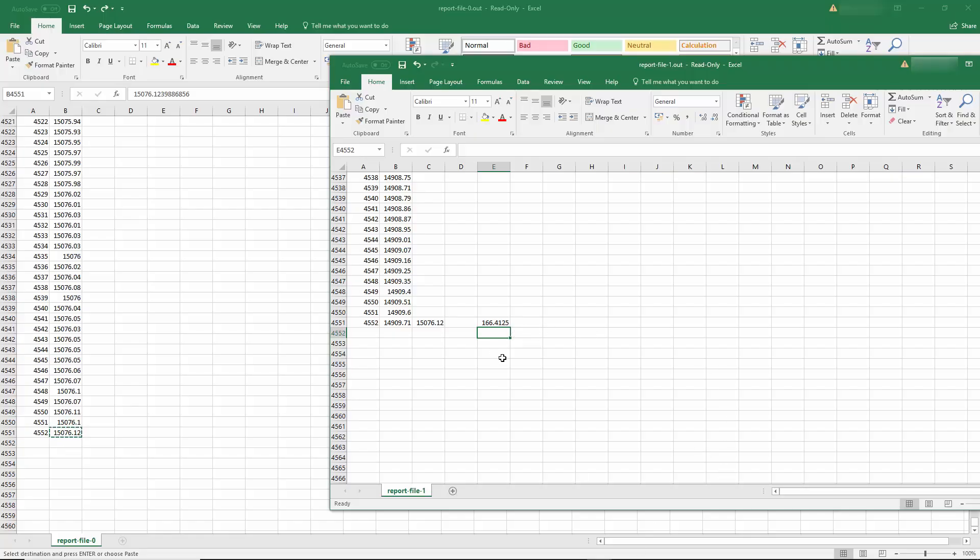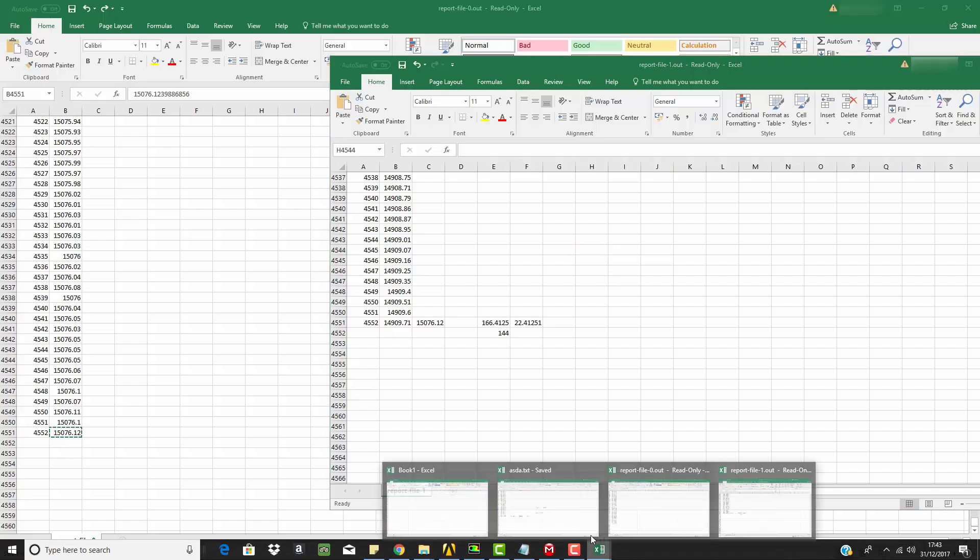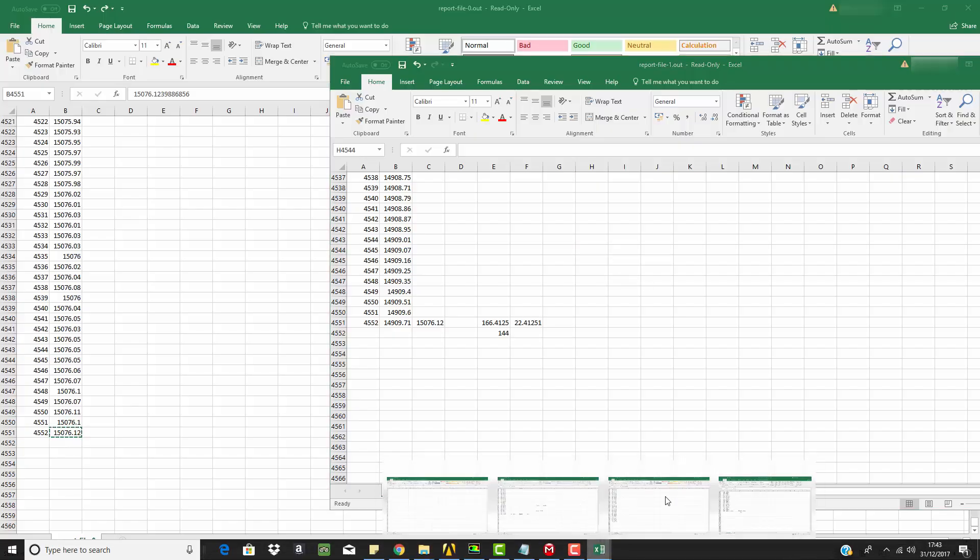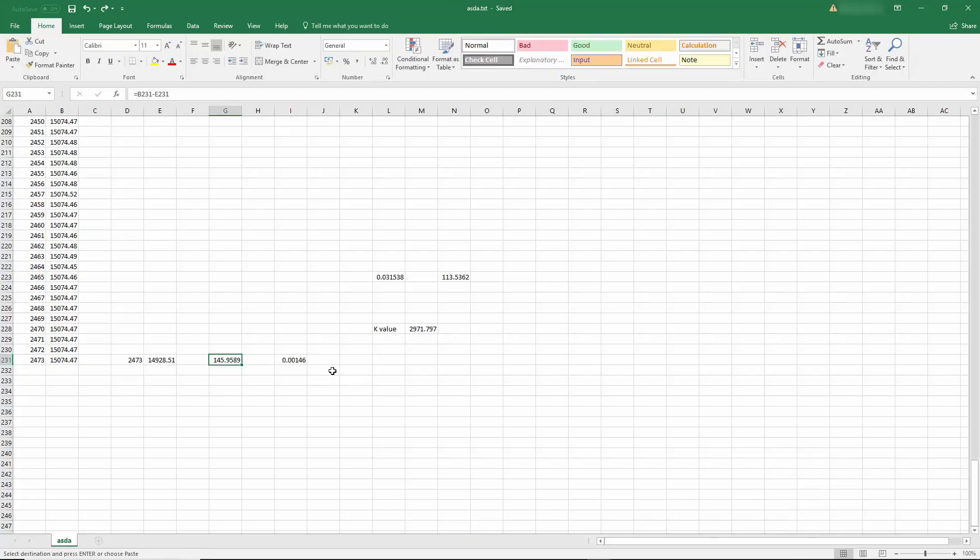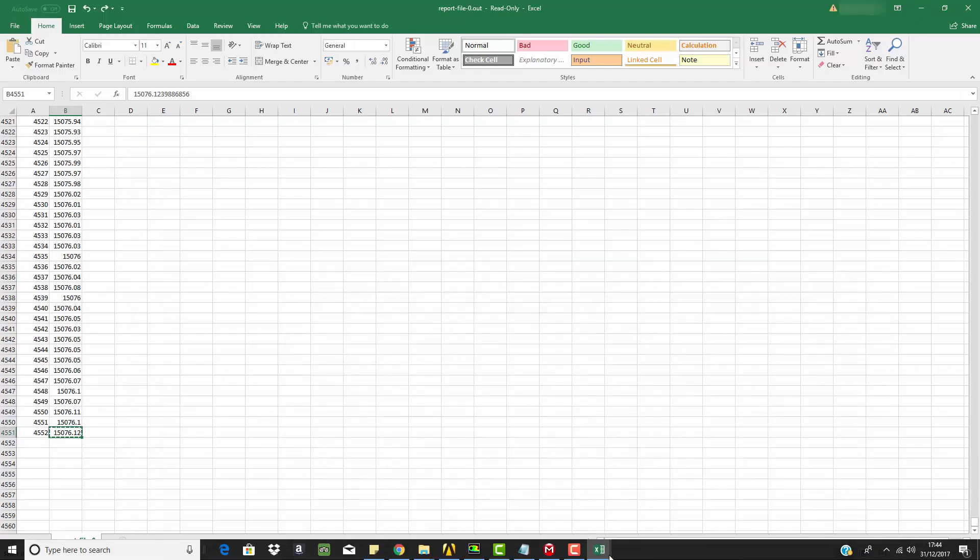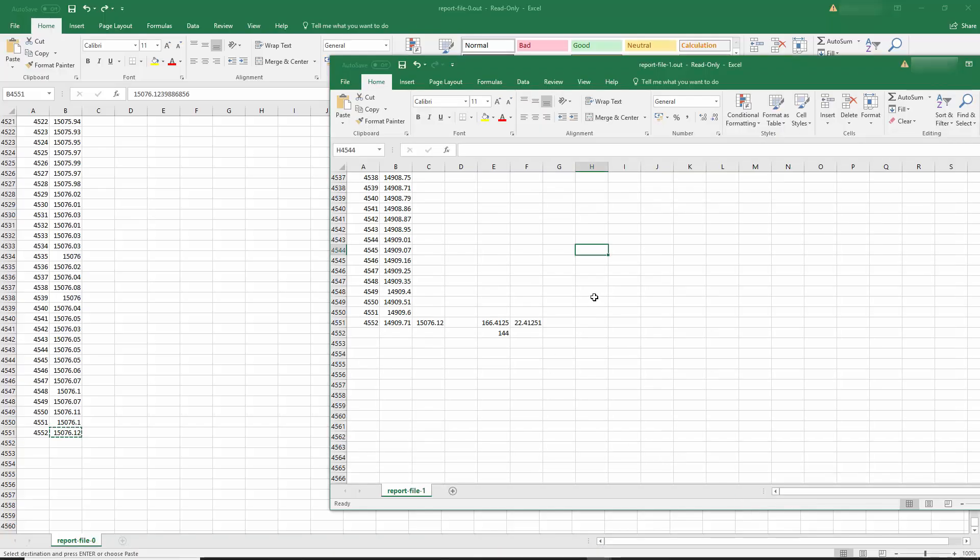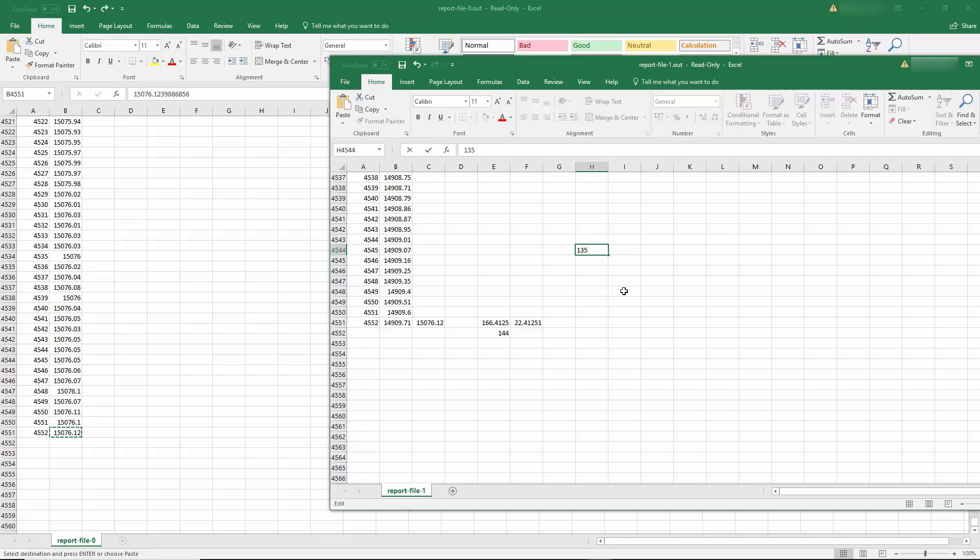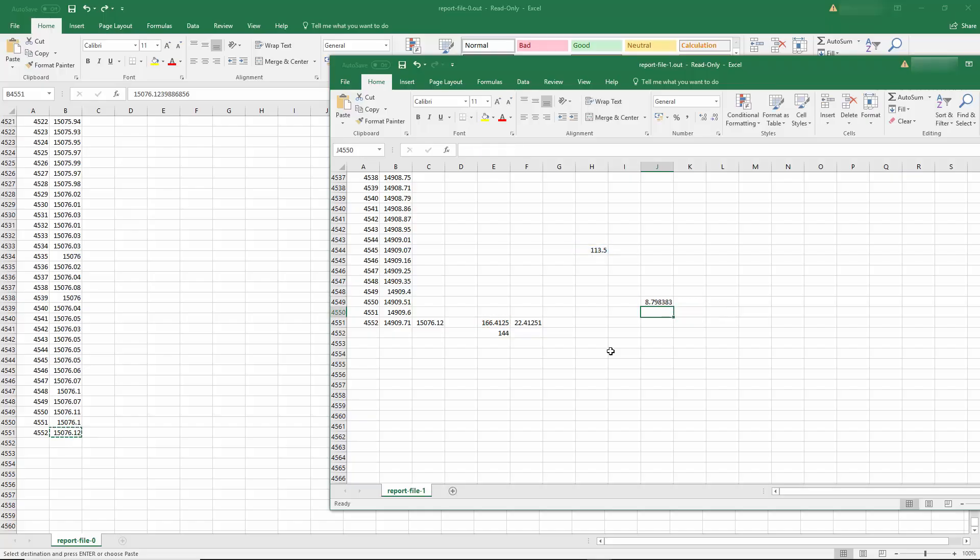But in this particular case we have 166.4 Pascal. So if we just put it here, we have this minus that, we have 22.5 almost Pascal of difference between the two models. Now to calculate the k value again, so if we collect the previous information from the URANS model which is in here, we know that the flow rate is 113.53 cubic meter per hour. So we go back, 113.5 cubic meter per hour. So it's this divided by the square root of 166.4.